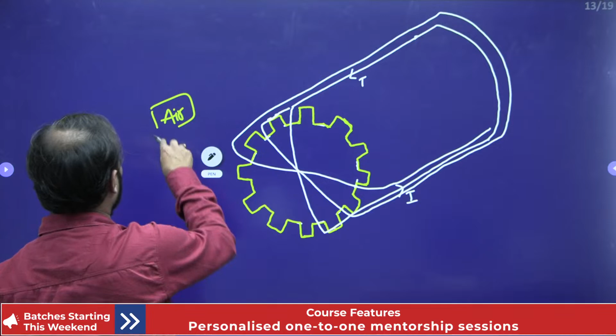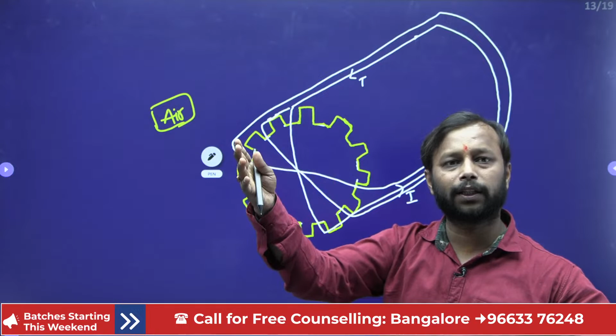Done. Now suppose you choose a wire of aluminium, then definitely it will have a higher cross sectional area, and for a higher cross sectional area this gap has to be wider when compared with copper. So whenever you choose the wire to be aluminium, the slots or the gap has to be higher. Therefore the size of the machine is going to be higher and the cost of such a machine is going to be higher, which is not economical for the consumer.